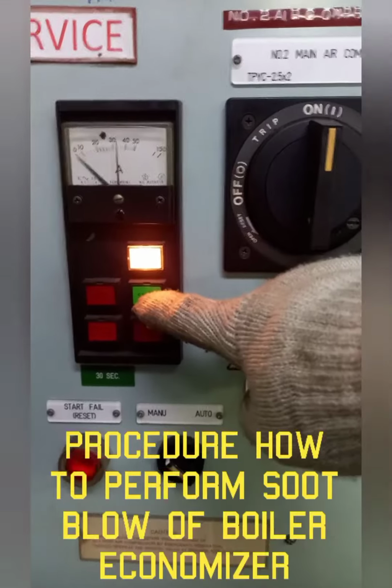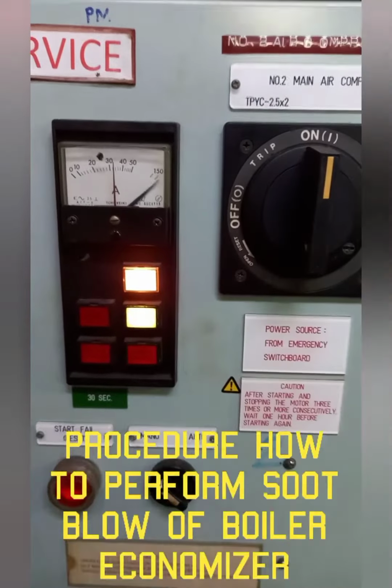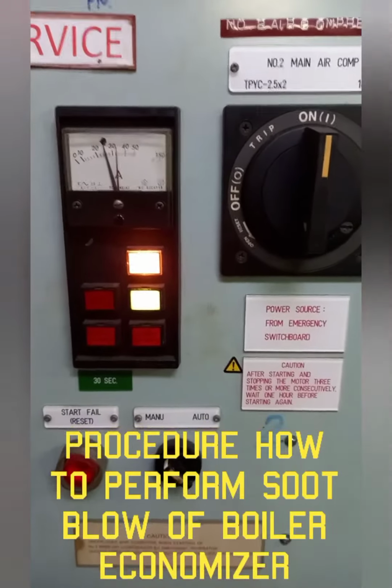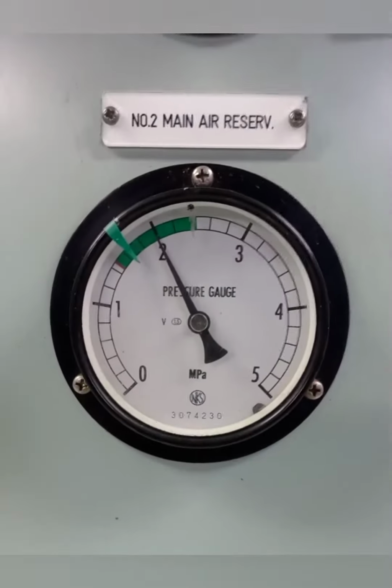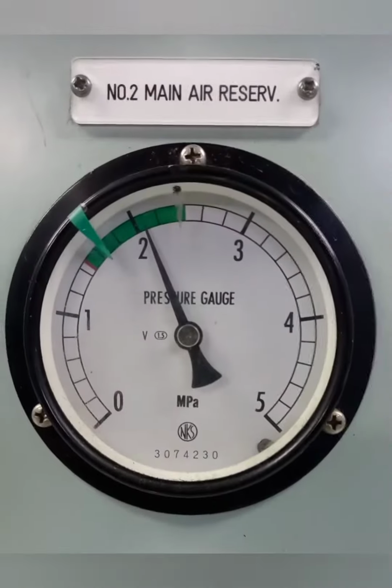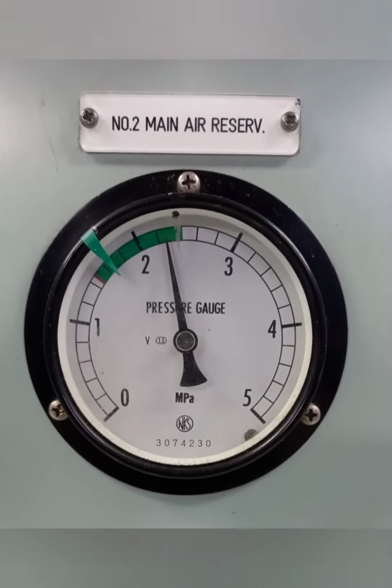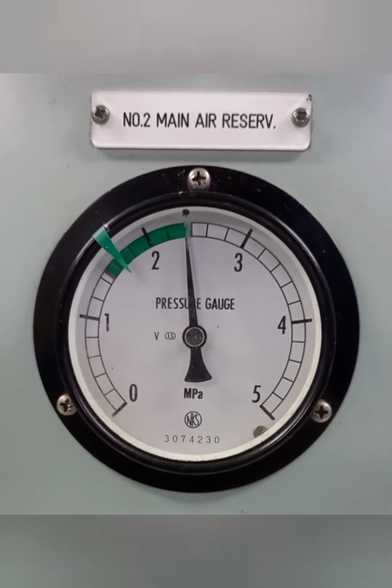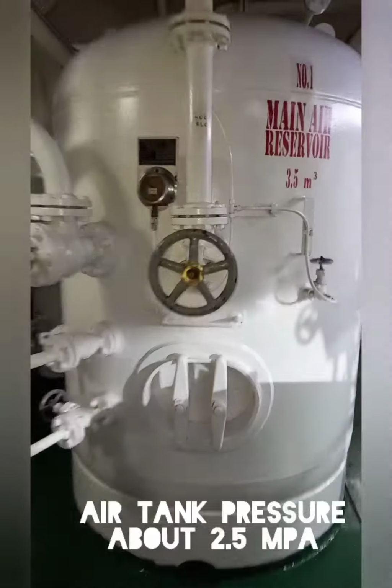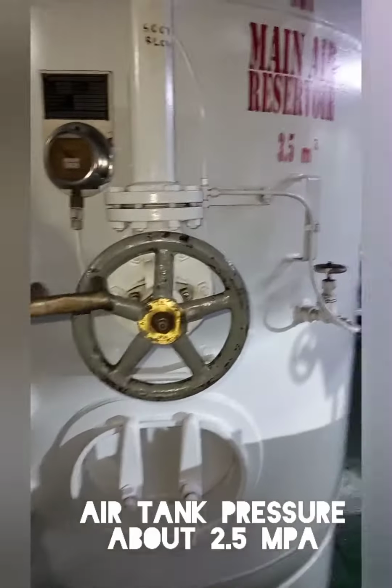Number 1. Start the air compressor and raise the air tank pressure to about 2.5 MPa. Make sure that all soot blow valves on boiler sides are closed. It needs over 1.8 MPa air pressure so that the high pressure air soot blow performs sufficiently. Number 2. Open the main valve on the air tank side.